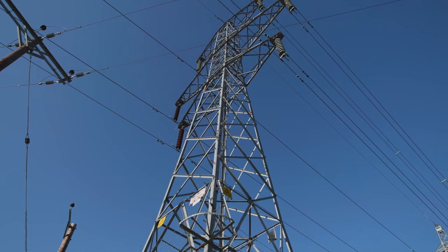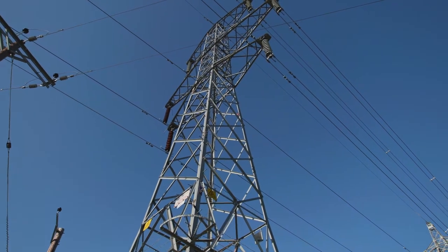What's come out of those results is that the algorithms at this stage were not sensitive enough to identify the change in electrical characteristics as the line was lowered, and as such, Kelvotech are now going through a refinement of those algorithms. We'll also be carrying out further controlled testing ourselves by applying faults to the network to accelerate that learning, shall we say, to ensure that we have sufficient data to prove the concept by the end of the project.